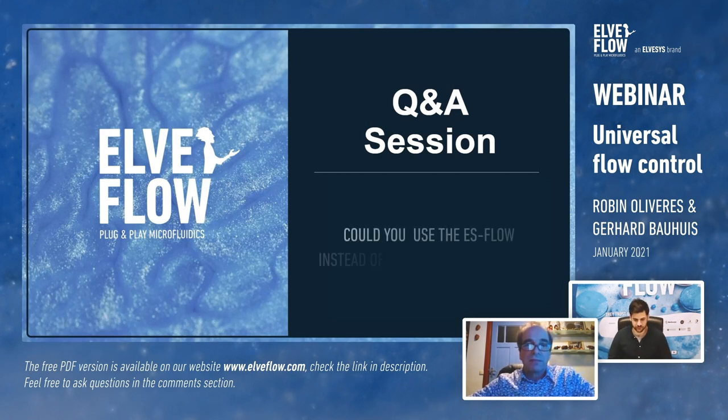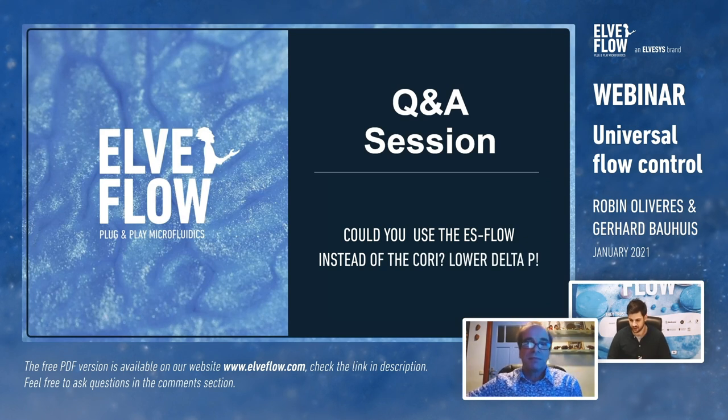Question from David about using the ES-Flow instead of the Coriolis. The ES-Flow is Bronkhorst's ultrasonic instrument, and you can use it, but it needs to be implemented in the Elveflow system. However, this sensor doesn't address the microliter flow rate range — it goes down to only four milliliters per minute, whereas most microfluidic applications relate to the sub-mL range. It would be handy as a non-contact sensor, but it's not the best fit.